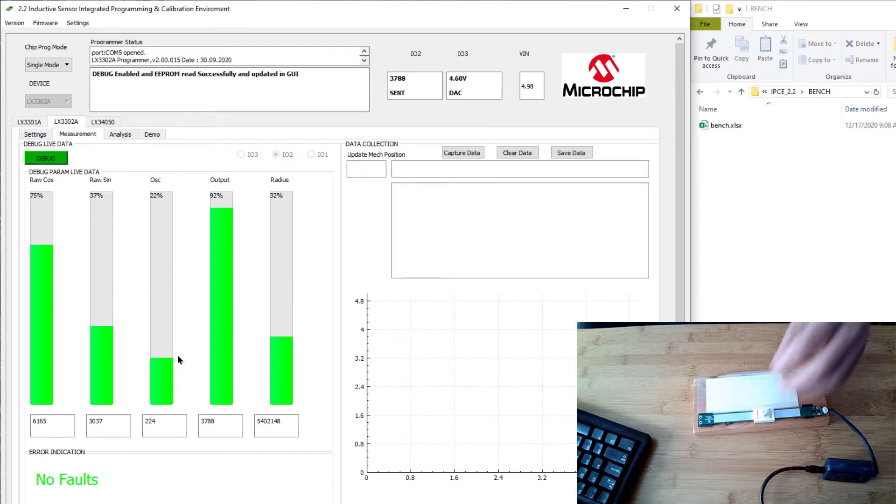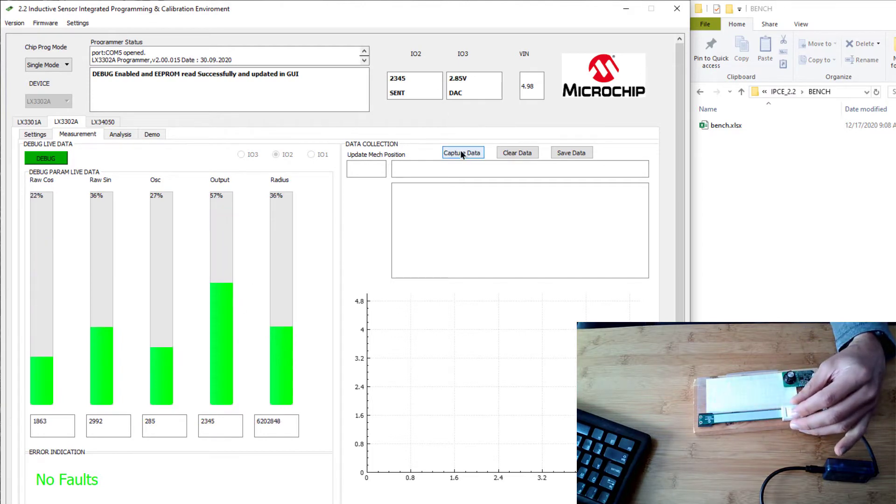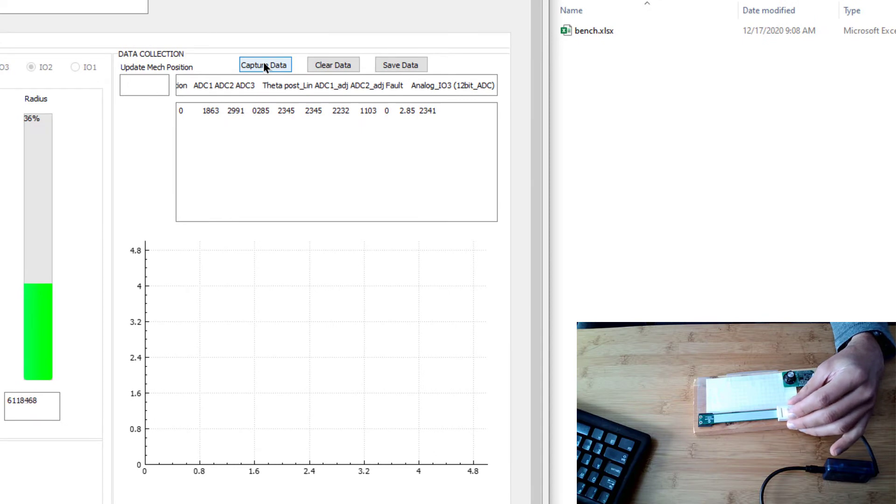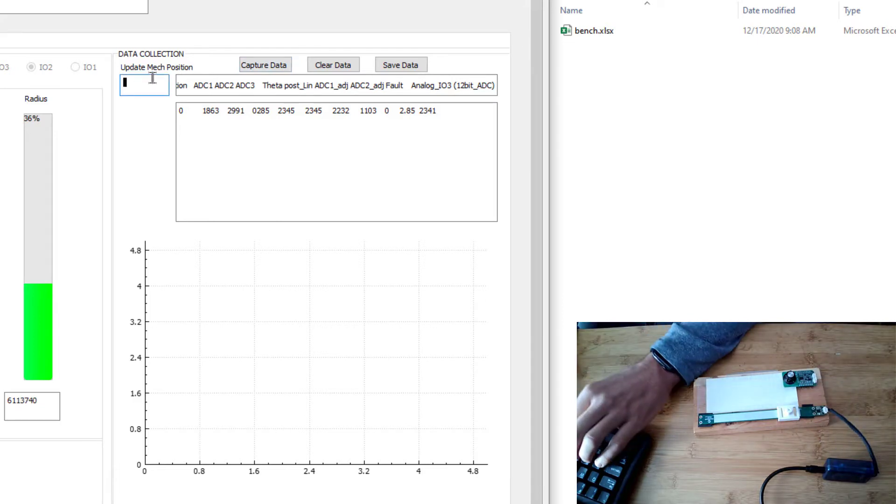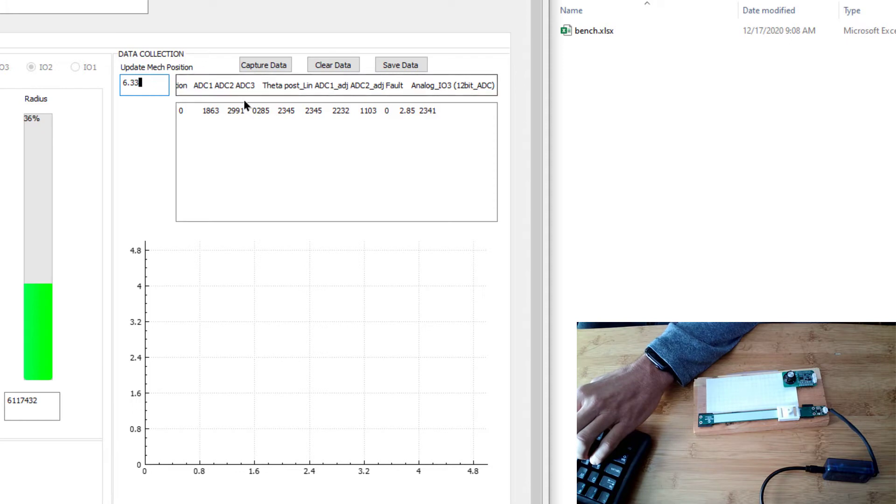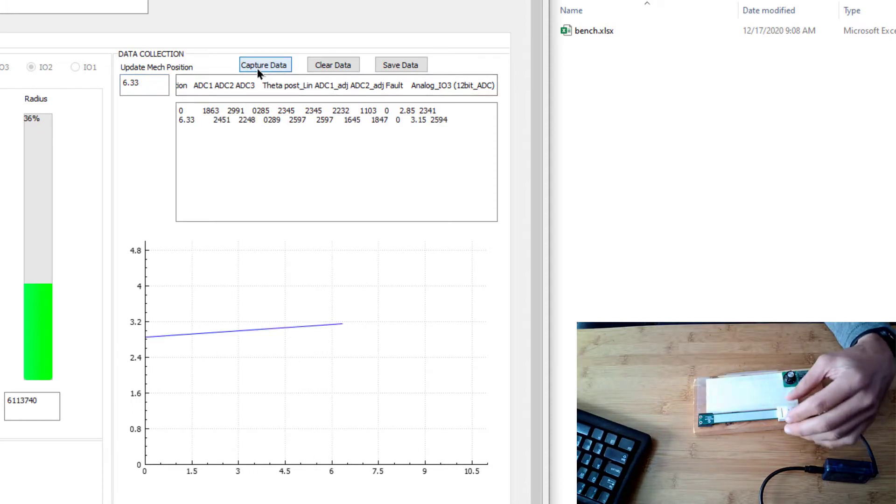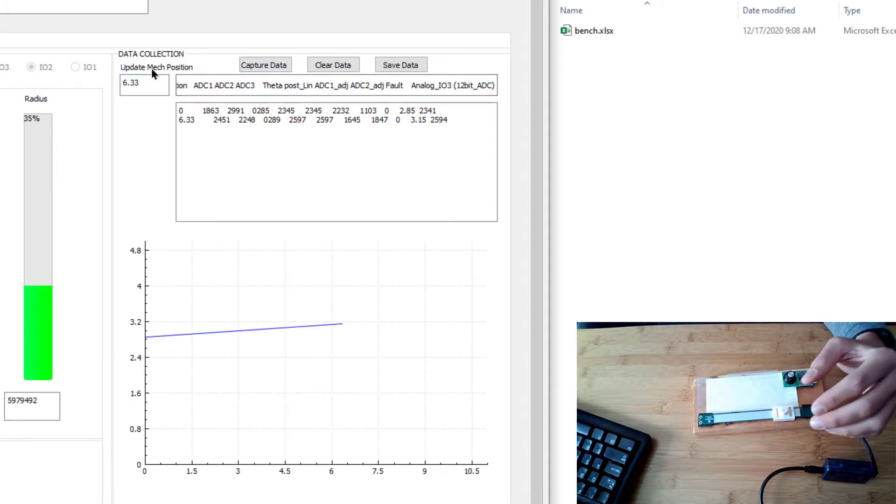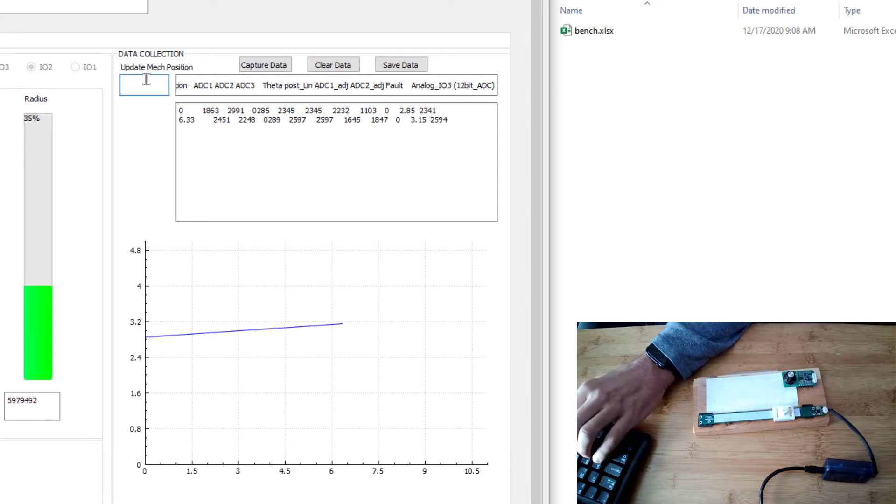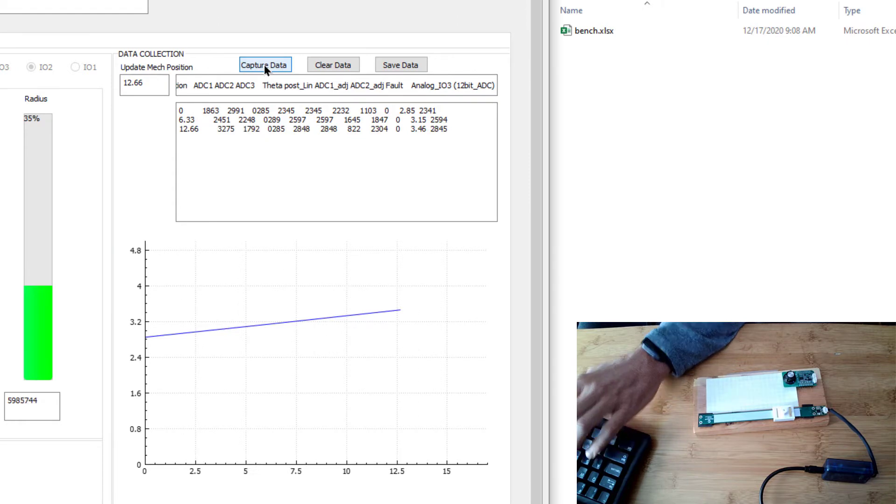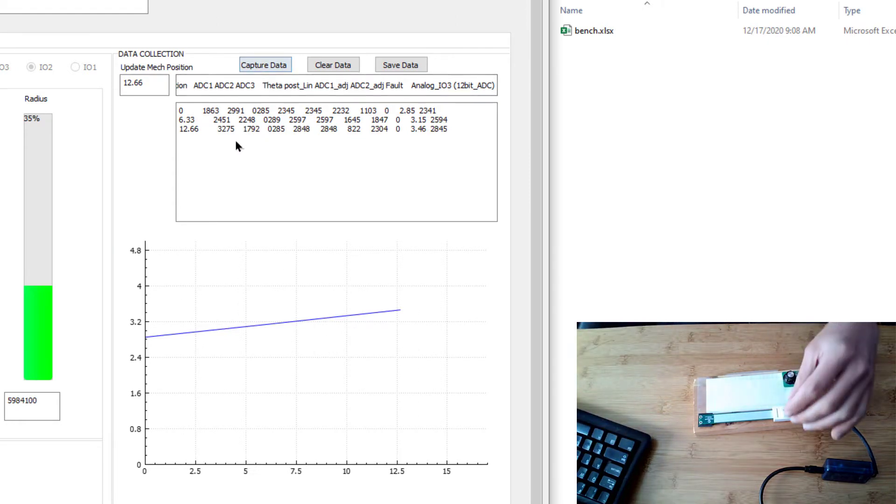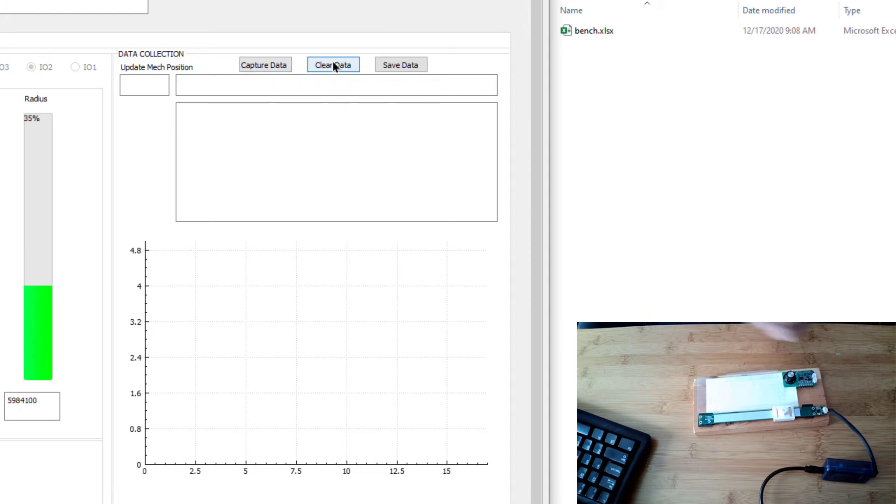With this, I'm going to move the target to the start of the measurement range and capture data. Then I'm going to go to the next block on my graph paper. I'm using my graph paper to help me measure the mechanical position, which I know is 6.33 millimeters, and I press the capture button again. I go over here one more to 12.66 millimeters and hit the capture button. I can continue down the line and do this until we get to the end of the measurement range. I'm going to do a slightly different technique which I will show you.